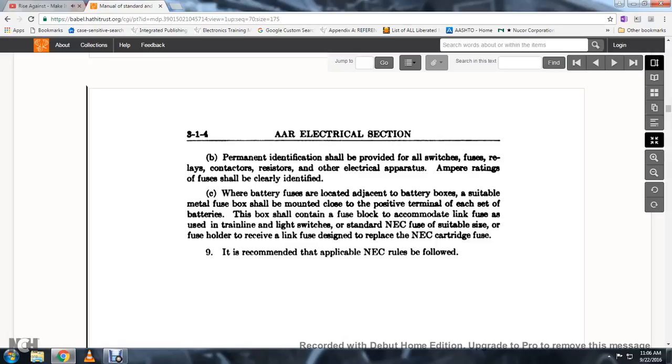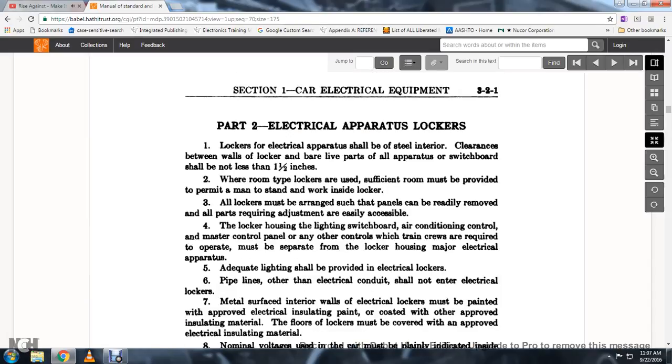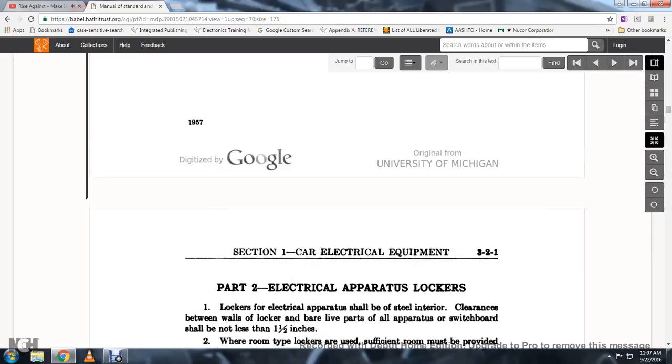Permanent identification shall be provided for all switches, fuses, relays, contactors, resistors, and other electrical apparatus. Ampere ratings of fuses shall be clearly identified. When battery fuses are located adjacent to the battery box, a suitable metal fuse shall be mounted close to the positive terminals. Each set of batteries in the box shall contain a fuse block to accommodate the link fuse when using the train line light switches with a standard NEC fuse of suitable size. The fuse holder to receive the link fuse is designed to replace the NEC cartridge fuse. It is recommended that applicable NEC rules be followed.